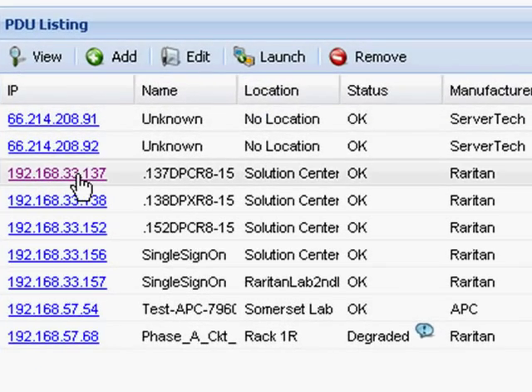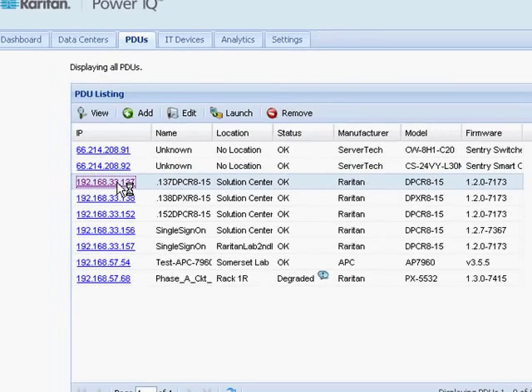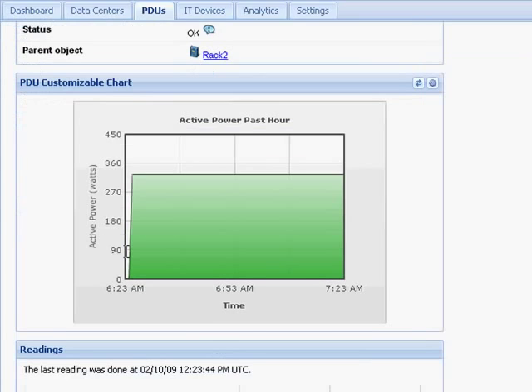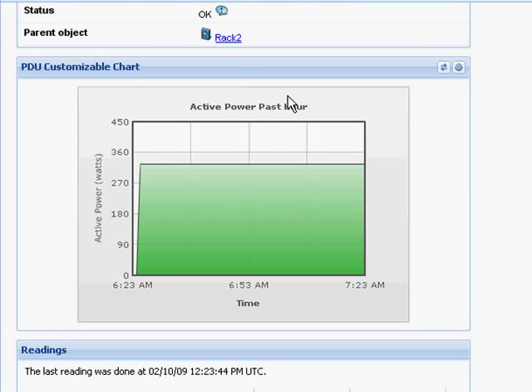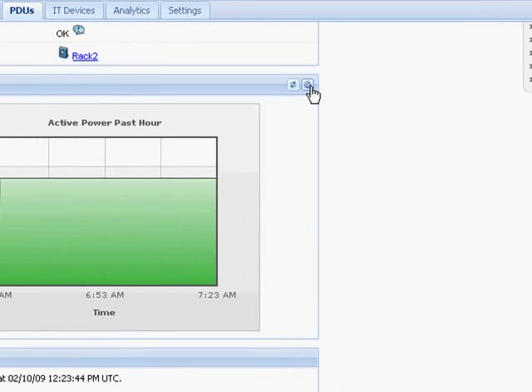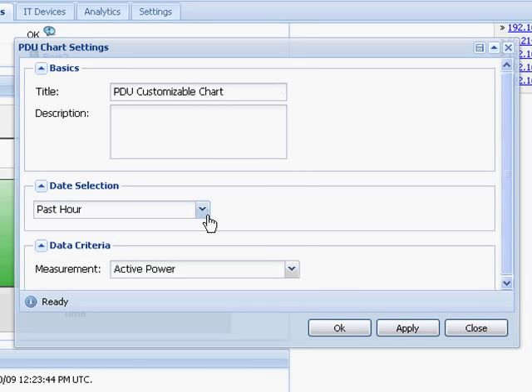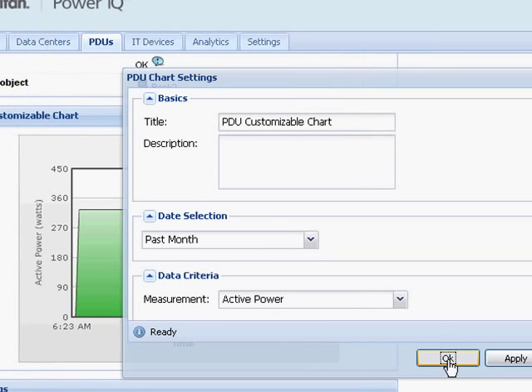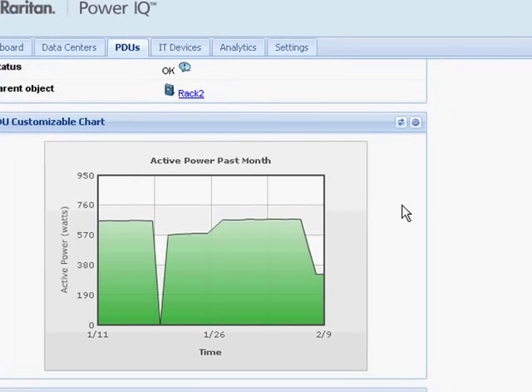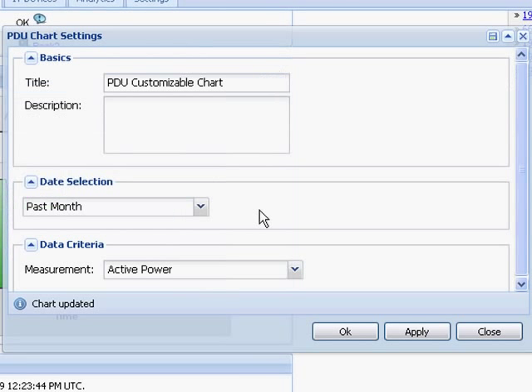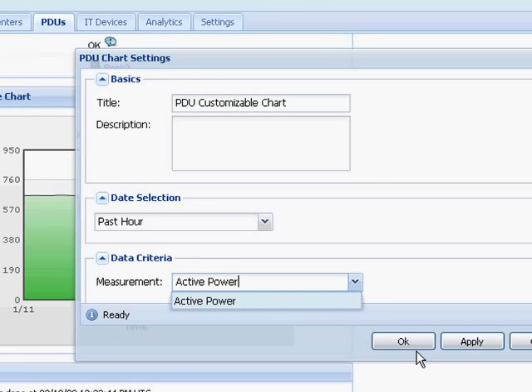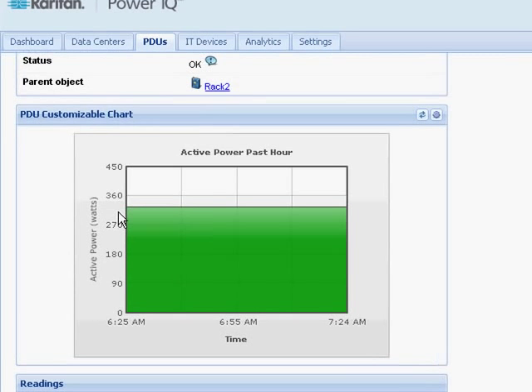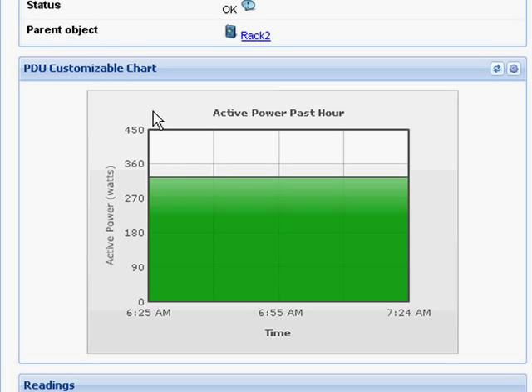The next step that I would probably take a look at is I would click the IP address of an individual PDU so that I go to the next level of detail and notice, am I graphing data? And sometimes people will go here and say their settings, and they'd pull up a graph, and maybe it's past month, and they've just installed the system, and they have past month. They might not show any data in the graph because there's not enough data in the graph. So if you start to play with the settings, make sure that you're going to past hour, so you're going to graph more current data. Make sure the measurement is active power. Select OK. You should be able to generate a chart of the total power used via this PDU.